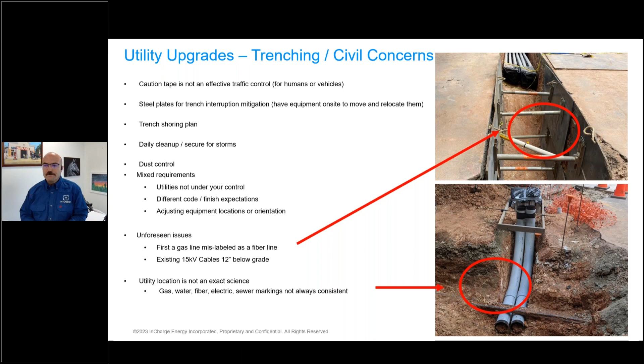So the final install, energize, pulling in the wire, make sure somebody's there. You want to make sure you get reports back on insulation resistance testing, or megger testing, because wire is easily damaged. You want to prove the insulation is good before it's turned on. Make sure they seal the ends.